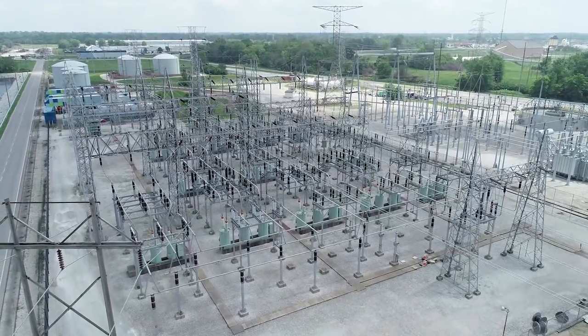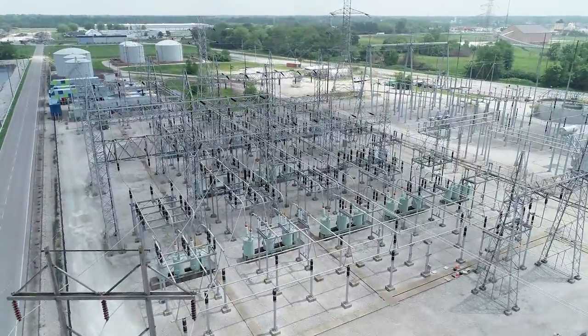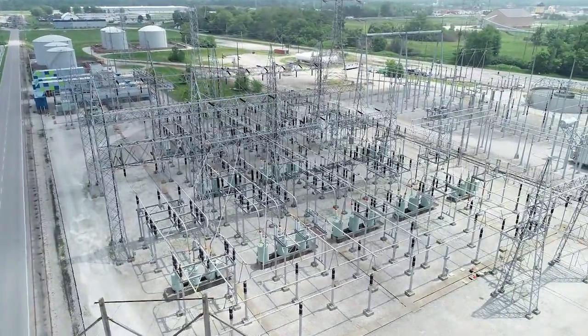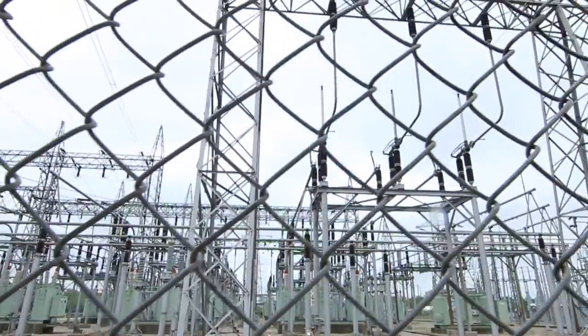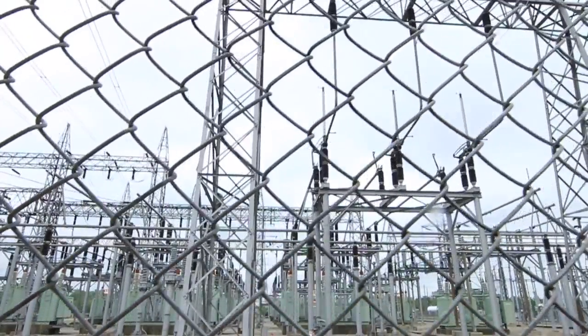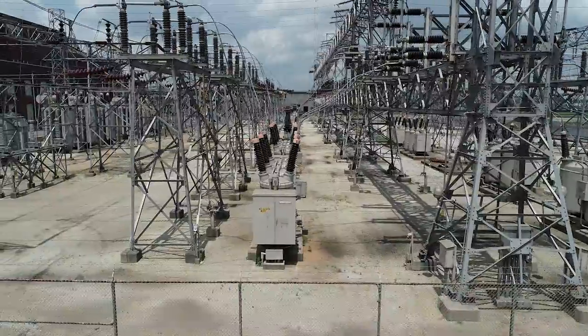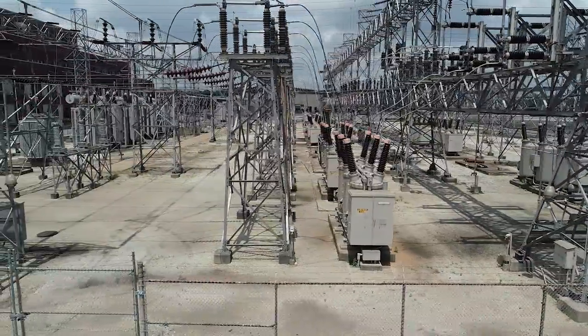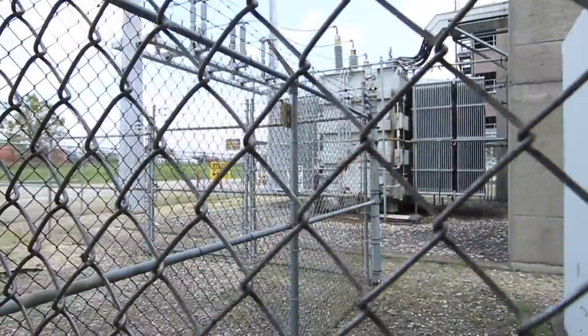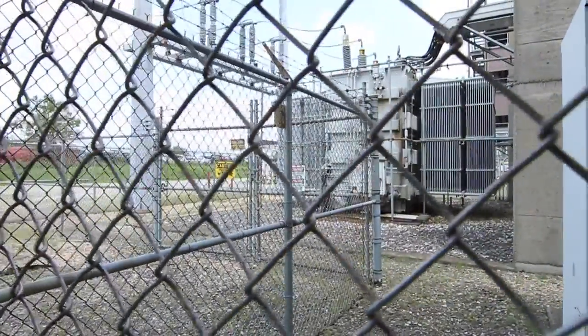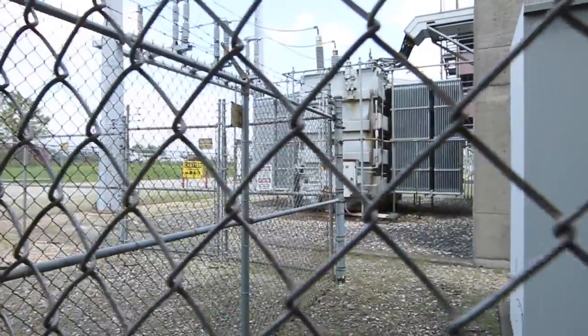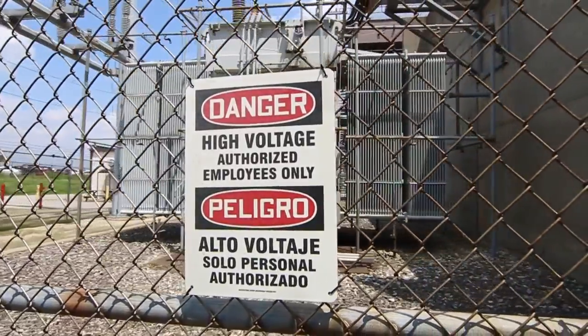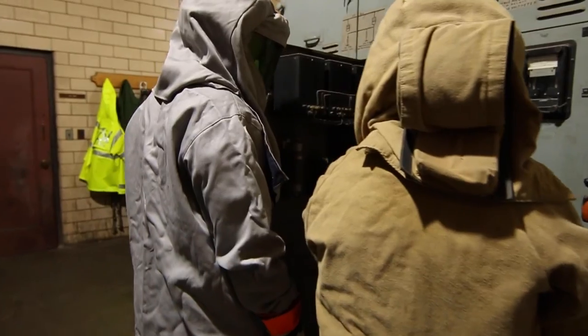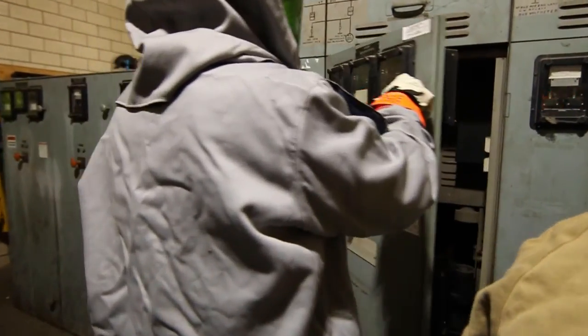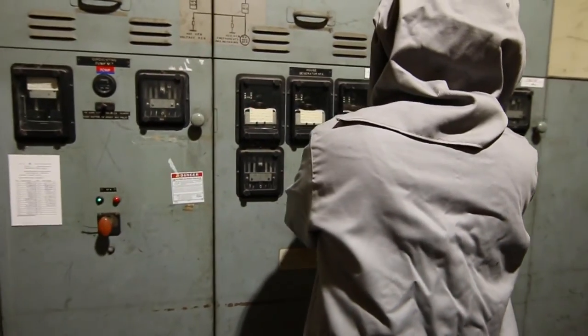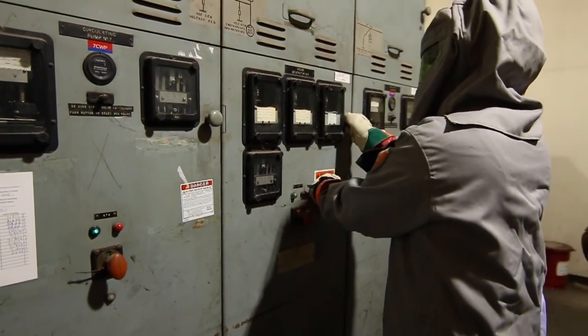When live parts cannot be placed into a de-energized state because de-energizing produces greater hazards or is infeasible due to equipment design or operational limitations, the task to be performed shall be considered energized electrical work and require the completion of an electrical live work permit before the work may begin. Only qualified electrical workers, QEW, may perform work under this type of permit. Your company is responsible for training and designating who is a qualified electrical worker.